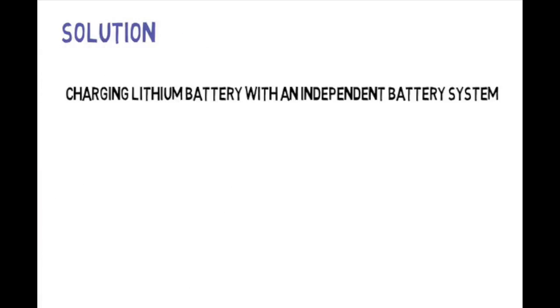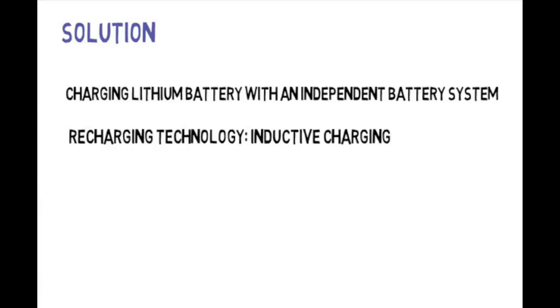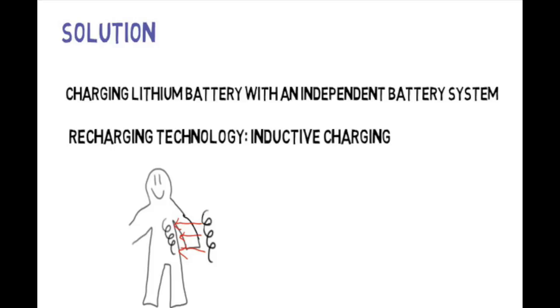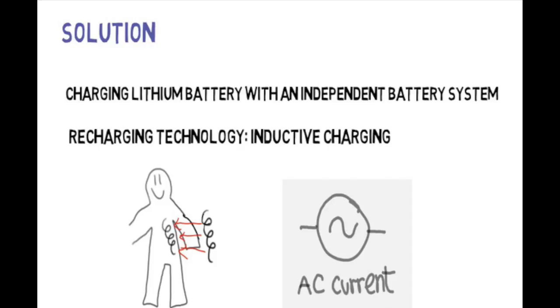By taking these criteria into consideration, we propose a solution that consists of a charging lithium battery paired with an independent battery system. The choice for the recharging technology is inductive charging, as it is relatively safe and has been used previously in many implants. Inductive charging works by having 2 coils, one inside the body and one outside. A high-frequency alternating current is passed through the coil on the outside. This causes a changing magnetic field, which causes a voltage to be induced in the second coil.